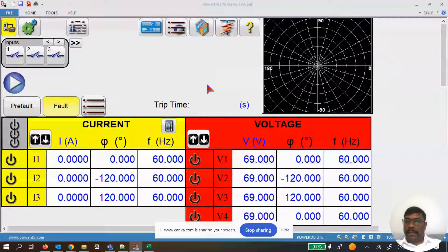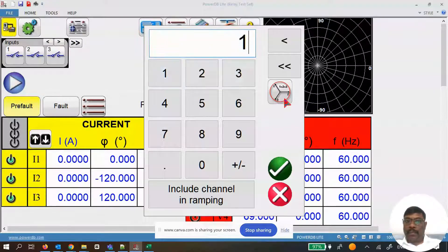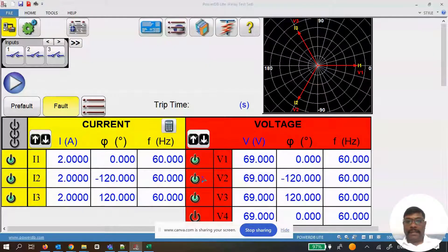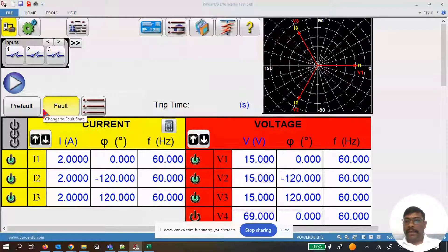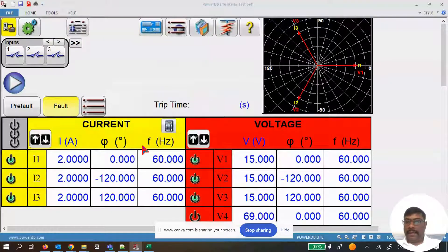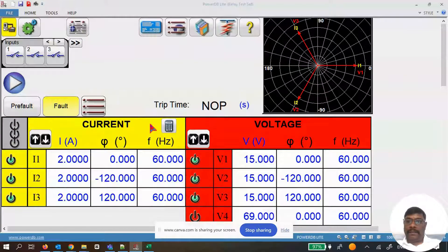The first test I'm going to run is the pre-fault/fault test from the home screen. I set the pre-fault to 1 amp, balanced and unbalanced phase angle, and 69 voltage balanced and unbalanced phase angle. The fault is set to 2 amps, fault voltage 15 volts, and max timer test time of one second. Running in simulation mode, the test stops one second after the fault.